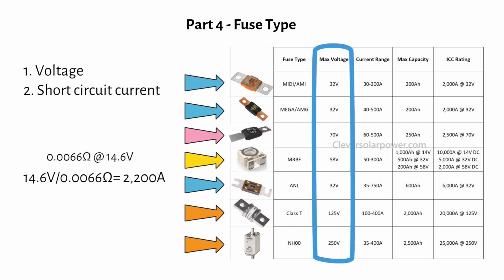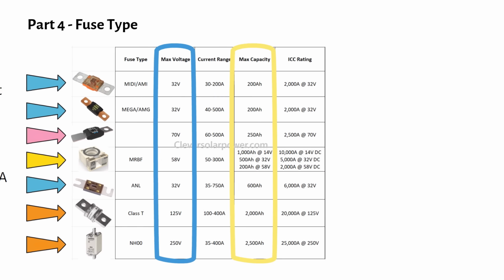So if your fuse can't interrupt that current, it will just sit there arcing, and the wire will start to melt and cause a fire. And no, do not rely on your BMS to break a short circuit. That's marketing. As you can see in the table, I have added the maximum recommended battery size for each fuse. This is based on the datasheets of my recommended fuse brands, which I will tell you later in the video.